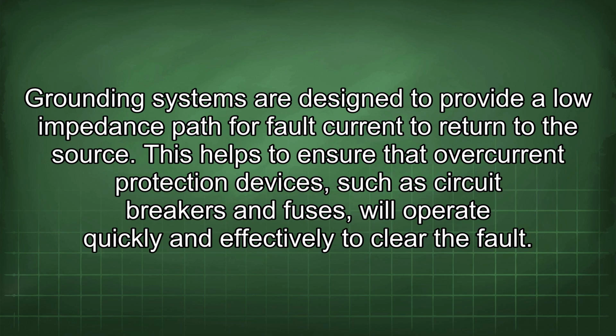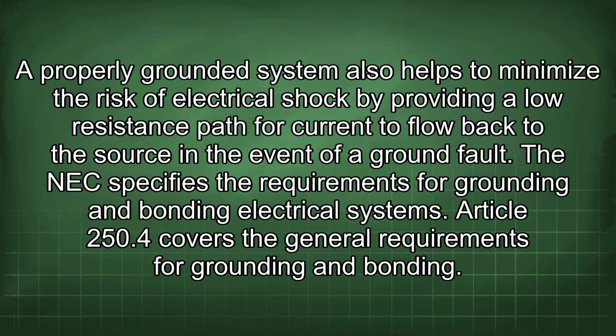Grounding systems are designed to provide a low impedance path for fault current to return to the source. This helps to ensure that overcurrent protection devices, such as circuit breakers and fuses, will operate quickly and effectively to clear the fault. A properly grounded system also helps to minimize the risk of electrical shock by providing a low resistance path for current to flow back to the source in the event of a ground fault.